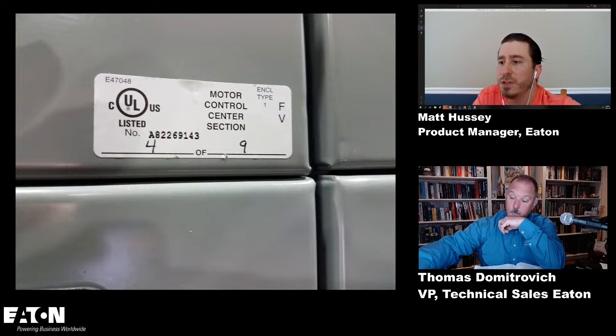Okay. What are these, 30 cycle structures? No, these are 3-cycle. So UL 845 identifies MCCs as 3-cycle products. Only 3 cycles. Yep. That goes back to, they were originally designed and built around the application with molded case circuit breakers, which are short circuit devices for 3 cycles. Okay, so that means I have to be in the instantaneous region of the feeder breaker with the bolted fault current, right? That's correct.